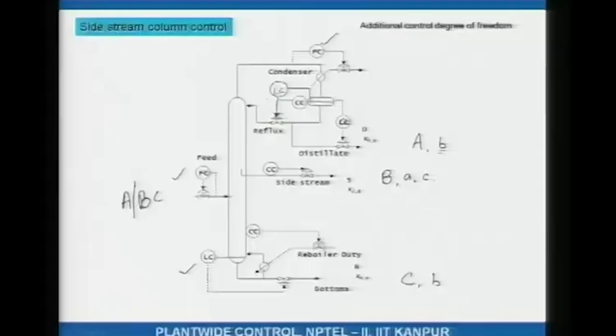If the amount of impurity, that is component B, in the distillate is increasing, what you would do is reduce the distillate. What that would do is cause the reflux to go up, and what that in turn would do is the flow rate of distillate will go down, and therefore, since the reflux has gone up, it will prevent the B from going up the top, right.